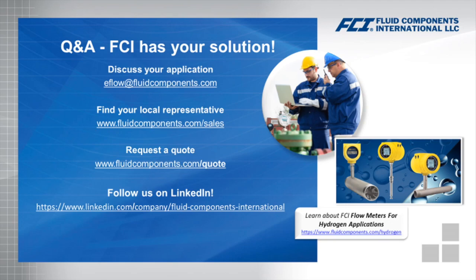Typically, if you want to get a lower range, you'd want to go down in line size to get the velocity higher and above the Reynolds number. You've got to keep in mind, if you go larger, that actual velocity is going to drop, and then you'll be on the low end. It really comes down to what's critical, a high flow or a low flow measurement. Again, there are solutions out there that, even with a 1-inch line, if you're transitioning through that zone, you can still do it. You just have to look at what the overall result is, again focusing on that min-max flow. And with those solutions, your accuracy should be as good as if there wasn't a transitional zone there at all. Hope that answers the question.